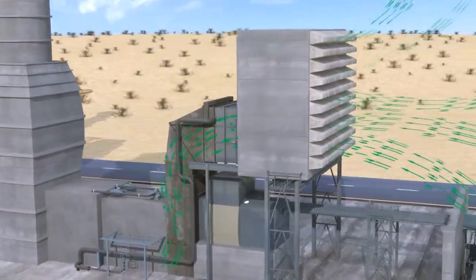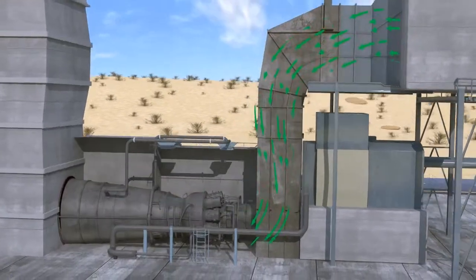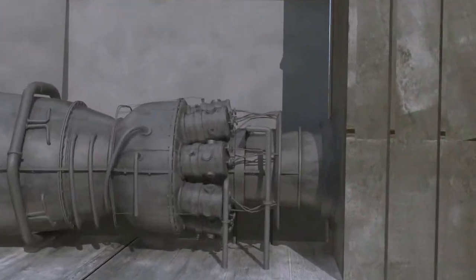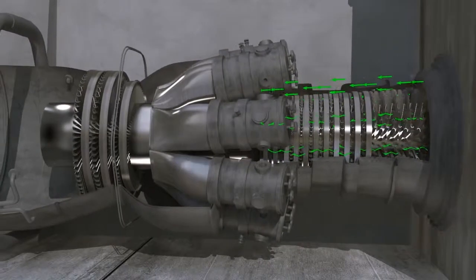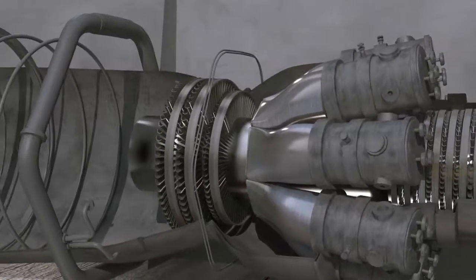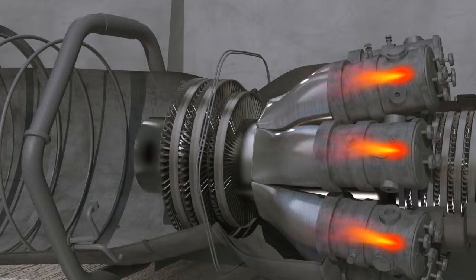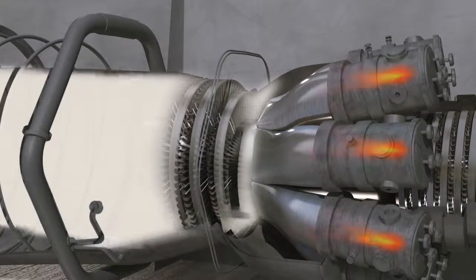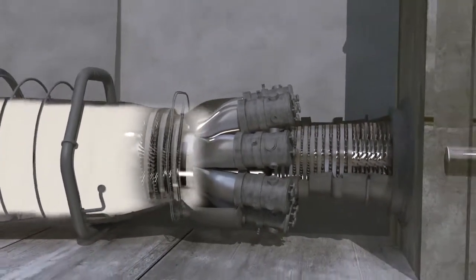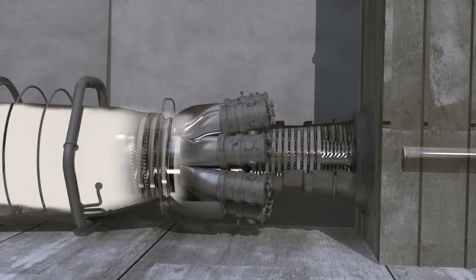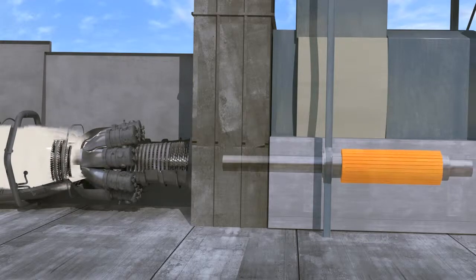In the gas turbine, fresh atmospheric air flows through a compressor that brings it to higher pressure. Heat is then added by spraying fuel into the air and igniting it, so the combustion generates a high temperature flow. This high temperature, high pressure gas enters a turbine where it expands down to the exhaust pressure, producing a shaft work output in the process. The turbine shaft work is used to drive the compressor and the electric generator that are coupled to the shaft.